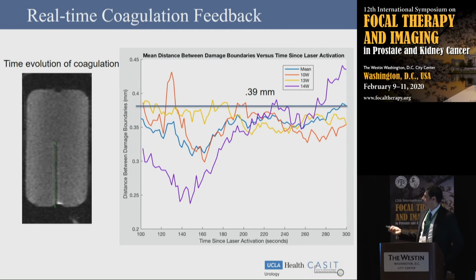We also looked at real-time coagulation feedback. So we used the temperature information to actually map out what the coagulation front was doing. So this is a time series showing the coagulation evolution in a patient, or sorry, in a phantom. And you can see at multiple power levels, there was an average error of predicting the actual coagulation zone at all time points of about 0.39 millimeters. Keep in mind this is in phantom.